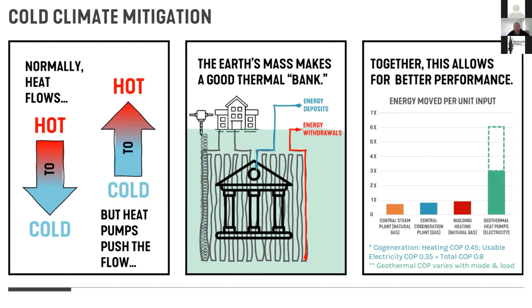A key to doing those really low entropy systems is actually the design temperature of what we're trying to deliver to the space. So classic cold climate is to take a 2000 degree flame, make 250 degree steam, run that through a heat exchanger to make 180 degree water, run that through a building and deliver 85 degree air to a room so that I can make a room 75. It's insane. We're making something extremely hot just so that we can make something relatively neutral.